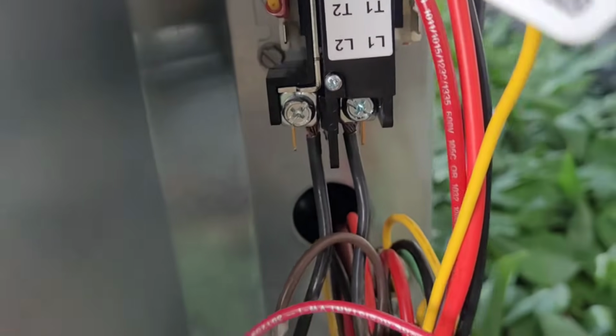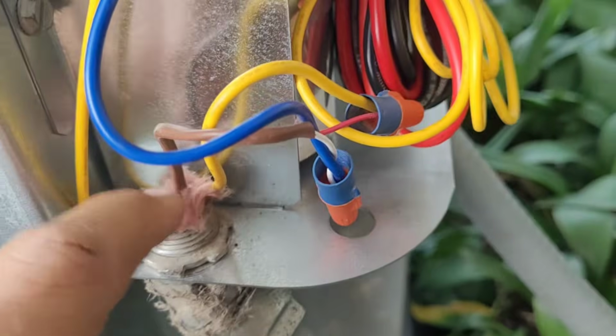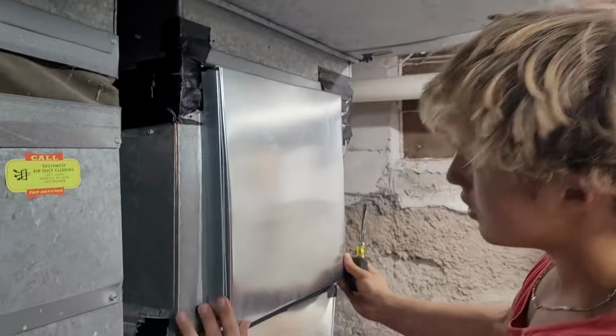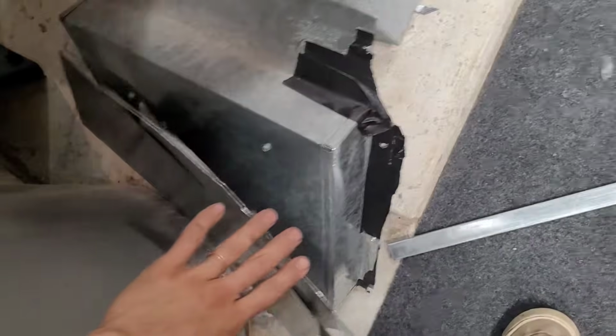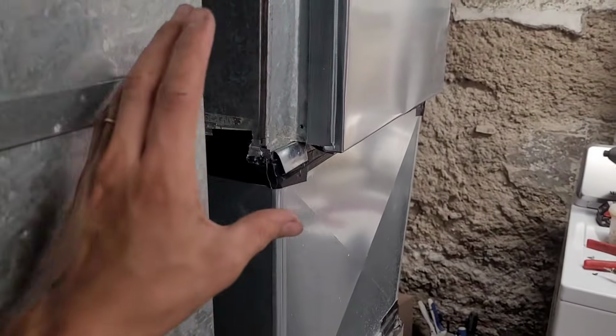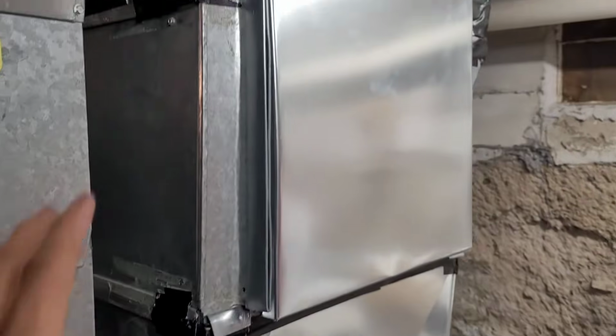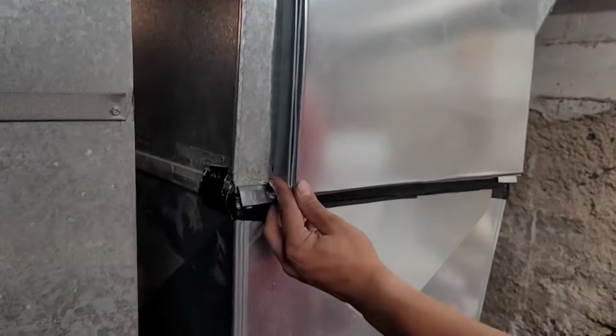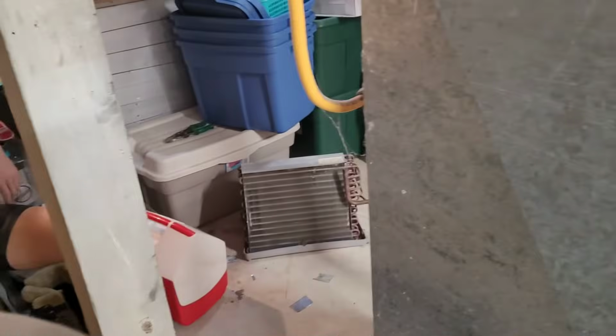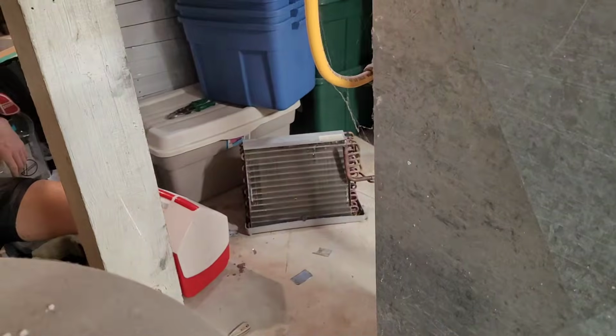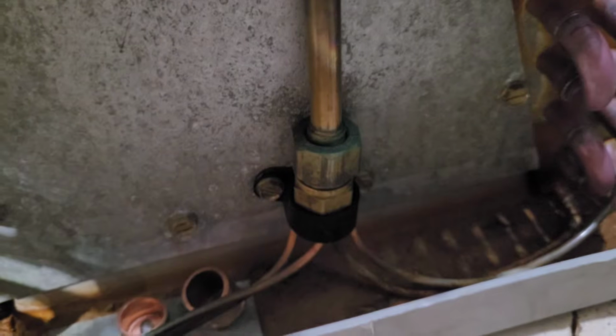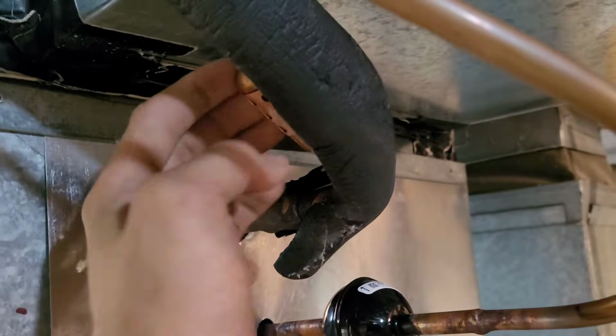And there's the wiring hooked up. Kind of interesting, they put some insulation in there to keep mice from going down into the conduit, I guess. So we had to, same thing as the other people, we had to build an extension out on this side of the ductwork because it's a very strange size of duct. And the old coil was like super narrow for whatever reason. You can see the old coil had a fixed orifice, and of course our new one has an expansion valve, so we've got the bulb mounted here.